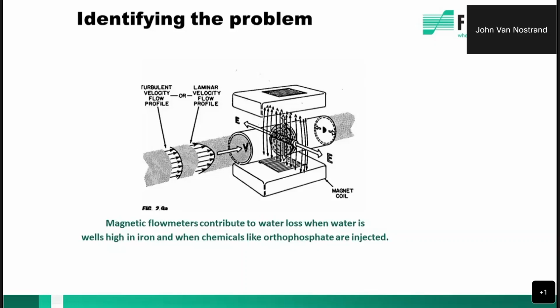And what Faraday's law states is that if you have a magnetic field and you pass a conductive material through it, it will output a voltage that's directly proportional to the velocity of that media. So there again, they're measuring the velocity of the media by picking up the voltage output that's a result of the induction that's being done by the magnetic field. And they're measuring that velocity and calculating volumetric flow based on the area of the pipe.